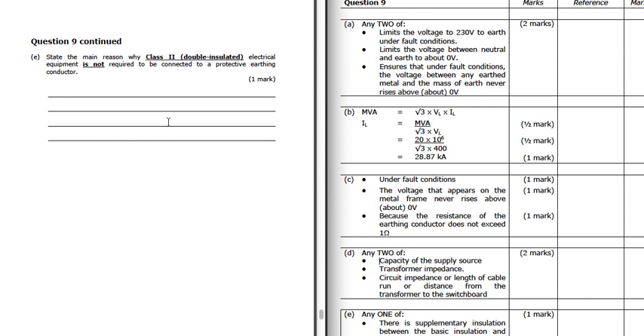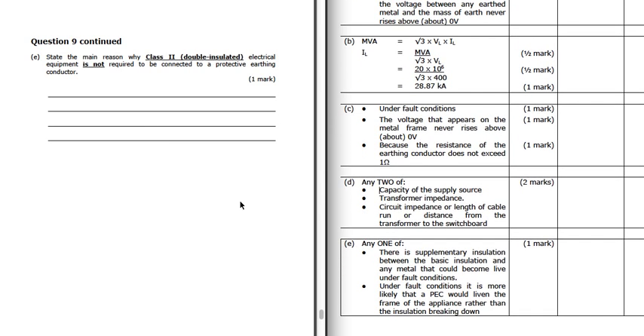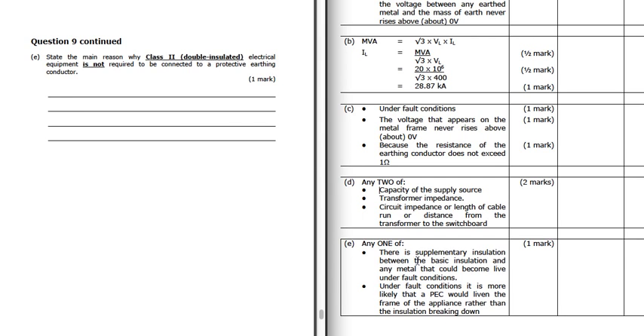State the main reason why Class 2 double insulated electrical equipment is not required to be connected to a protective earthing conductor. So we don't earth Class 2 equipment. And why don't we earth it? Well, because there's this supplementary insulation between the basic insulation and any metal that could become live under fault condition. So we've got two barriers between any phase conductor and any metal that someone could be touching that could become live. So not only have we got the insulation of the cable, we've got this secondary.